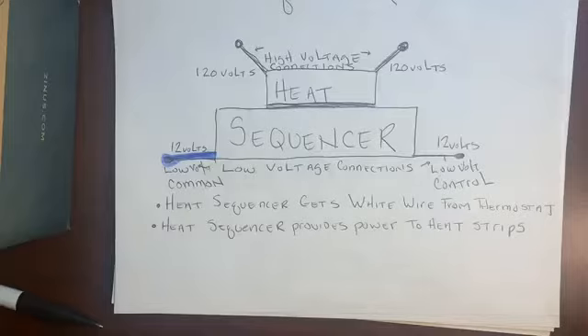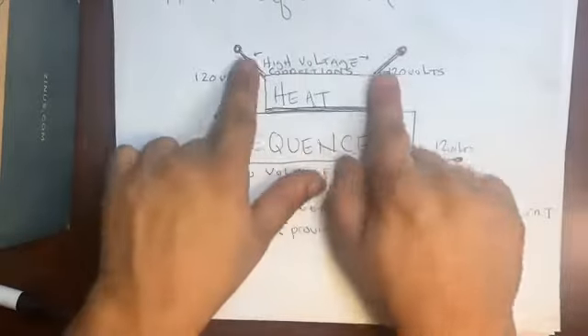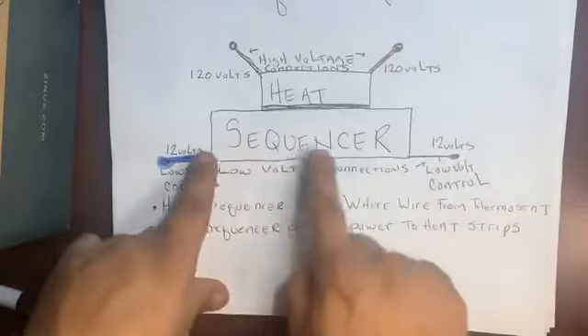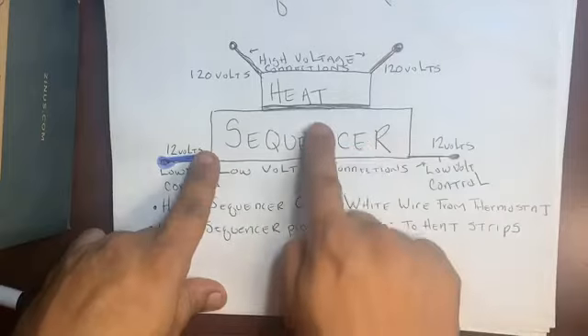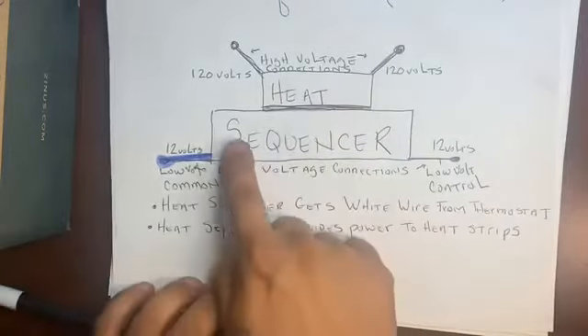We're gonna go over each relay, then we'll put them on the board and see how they work together. Heat sequencer. High voltage connections on the top. Once the low voltage gets 12 volts from each side, gets its 24 volts, what happens is there's a little bimetal in here that floats up. It takes a few seconds. It's about 15 to 20 seconds.